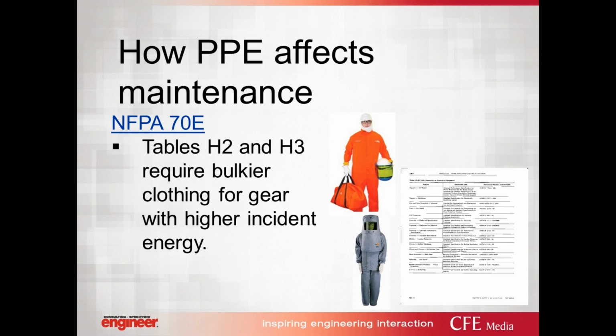How PPE affects maintenance. We actually get a chance to determine, while we're looking at these systems and building these systems, how PPE will affect maintenance over the lifetime of the building. NFPA 70E tables method typically requires bulkier clothing for gear with activities that have potentially higher incident energy.